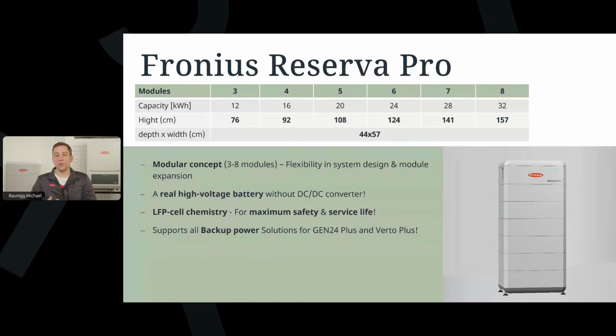Let's talk a little bit about the technical data of the battery system. As you can see, the Reserva Pro is a little bit bigger than the existing Reserva, meaning that the depth and width of the system is 44 centimeters by 57 centimeters. So although it is a bigger battery, it is still a compact sized tower. The height, of course, varies depending on how many modules you are installing. The smallest system with only 3 modules is 76 centimeters high, and the biggest system, with 32 kilowatt hours usable capacity, is only 1 meter 57 high. So even with the biggest system, it is nearly 160 centimeters in height, meaning even for smaller technical rooms or basement rooms, this should never be a problem to install the system.